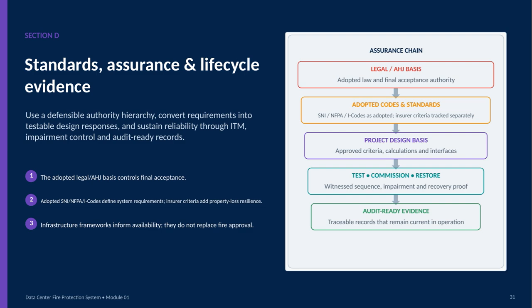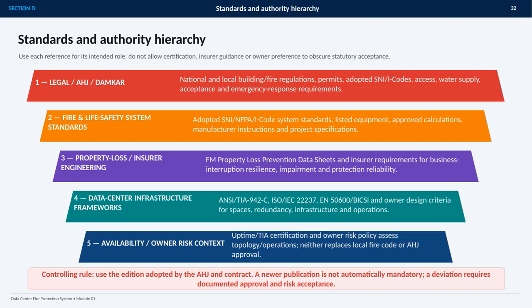That evidence connects the legal basis to the design to tested performance, and tested performance to dependable operation over the system lifecycle. This slide establishes the hierarchy we use when selecting and applying references for a data center fire protection system. The controlling principle is simple. Statutory acceptance comes first. Legal requirements, the authority having jurisdiction, and DAMKAR determine the applicable regulations, permits, access, water supply, acceptance process, and emergency response obligations.